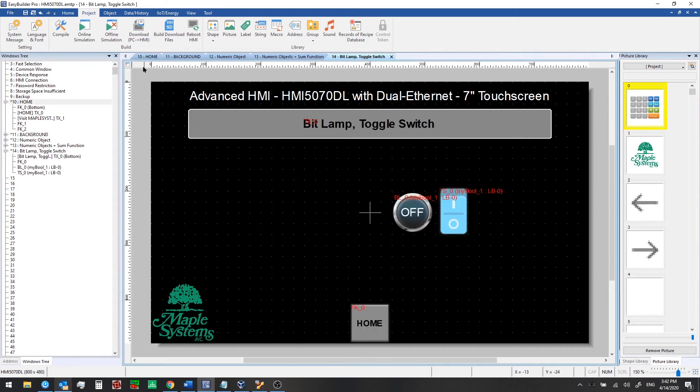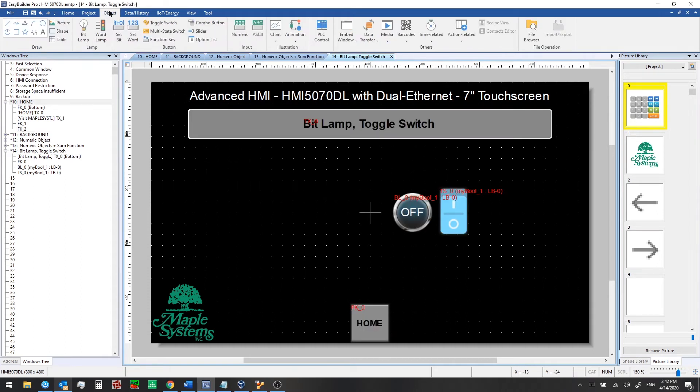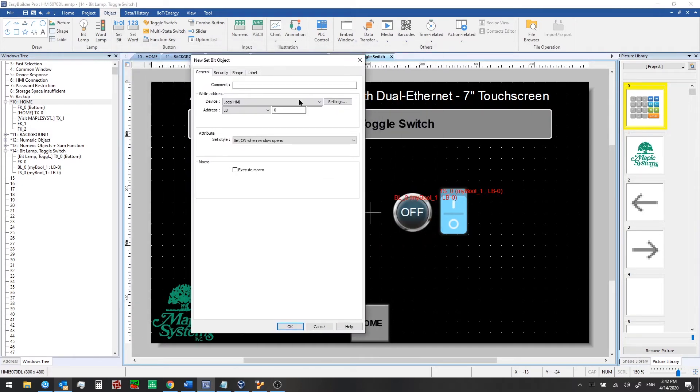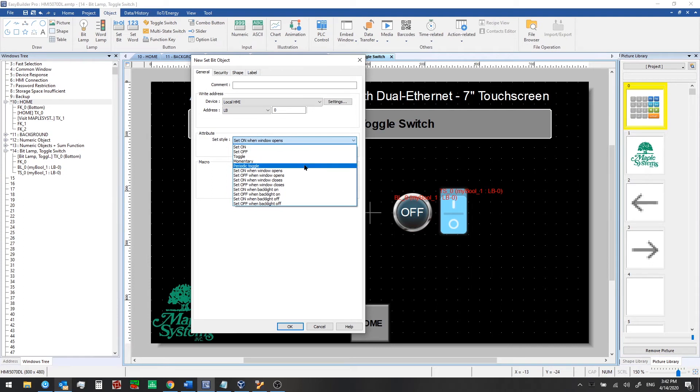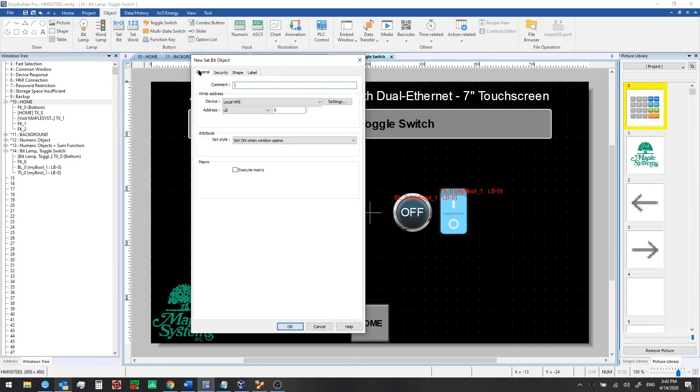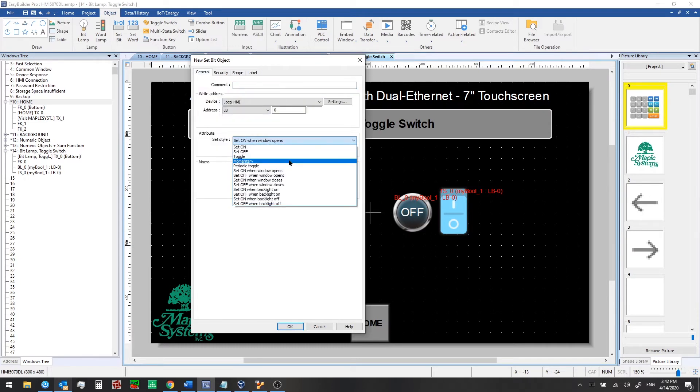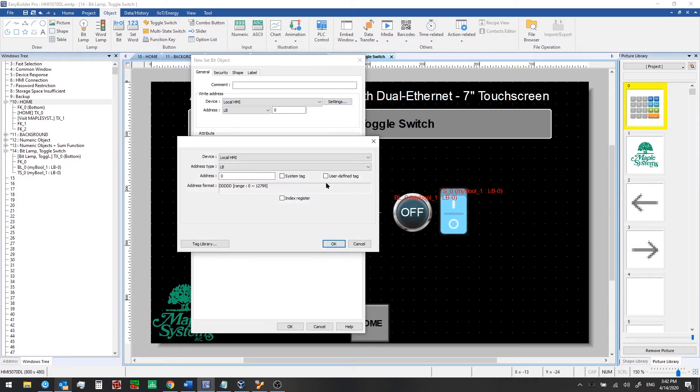We'll go back here and we'll talk about the set bit, which is another type of bit action or function that we can use. So here we have different styles that we can use. A set bit will generally be hidden. You'll be placing it on the window. Or if you want you can have a shape if you're using the toggle or momentary styles here. But for example if you want to set on a bit when the window opens, as in when you navigate or when an operator navigates to this window, we can do that with set on when window opens. So let's do that and do a quick test so you can see what it looks like.